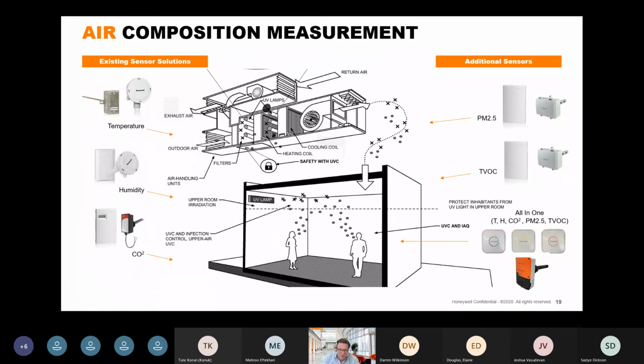Bring that into my world of plant and air handling units. So this is an air handling unit. In this instance, this really relates to a customer I was working with in London. They've been asked to implement the strategy changes, to implement no recirculation, plant running flat out. All of their air handling units are fixed 80% recirc. They haven't got a mixing box.